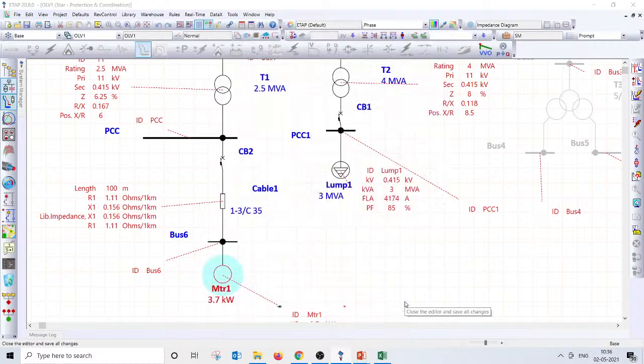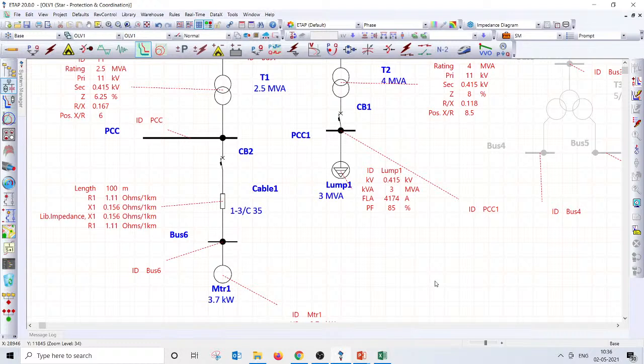All right, good. So now you have understood why we should not use a 3.7 kilowatt motor directly at PCC. One, this breaker you need to size for the full load current of the motor, which is too less, so the breaker rating itself is something like 10 amps, and this 10 amps breaker has to be designed to cater to 50 kiloamps or 65 kiloamps or 75 kiloamps. That's what you need to really look into. That's another important aspect. And when there is a fault at the remote place, the fault current is too low, meaning the short circuit current variation over the length of the cable is too much. That's the second issue.